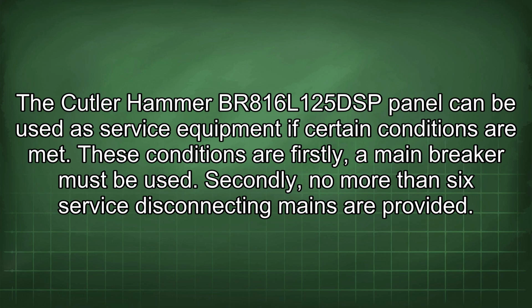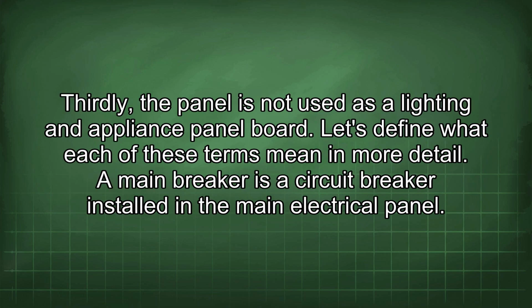These conditions are: firstly, a main breaker must be used. Secondly, no more than 6 service disconnecting mains are provided. Thirdly, the panel is not used as a lighting and appliance panel board. Let's define what each of these terms mean in more detail.